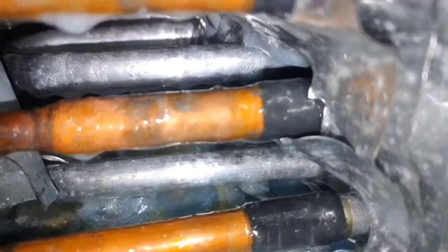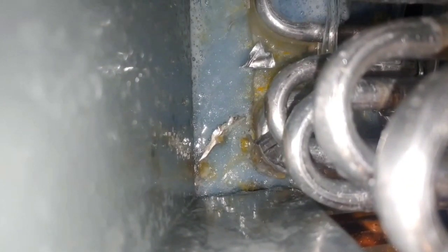I spent a lot of time looking for the leak - a couple of hours, two or three hours trying to find it because I knew it was there somewhere. I looked all over this end of the coil, sprayed it all down with bubbles. I was using the camera and the light to try to find bubbles forming, but I couldn't find them. I knew the leak was there because every time I turned my leak detector on, it would beep and alarm really bad.